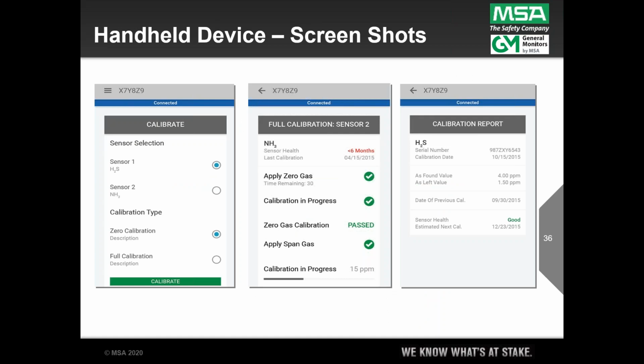Got a few screenshots. You can calibrate. You can set it up. You can get a cal report. This is what these three screens show. The calibration type, zero or full. Which sensor are we going to calibrate? You have green checks as you proceed through the calibration process, and when you get all done, you get a cal report. And as I said, it really makes life easy, especially if it's a remote site.